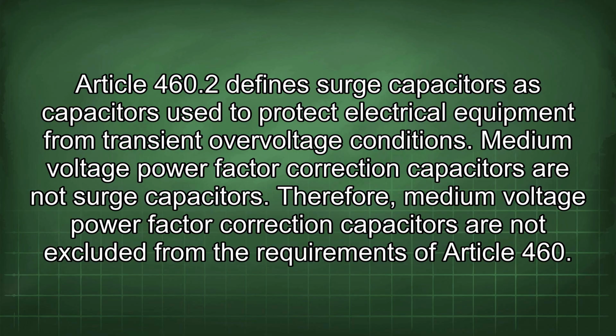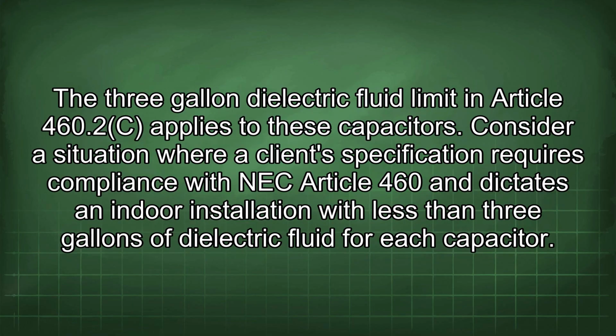Medium voltage power factor correction capacitors are not surge capacitors. Therefore, medium voltage power factor correction capacitors are not excluded from the requirements of Article 460. The 3-gallon dielectric fluid limit in Article 460.2c applies to these capacitors.